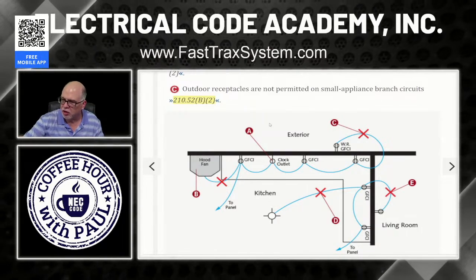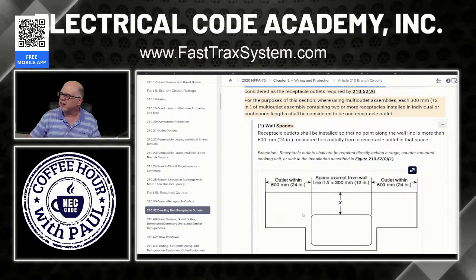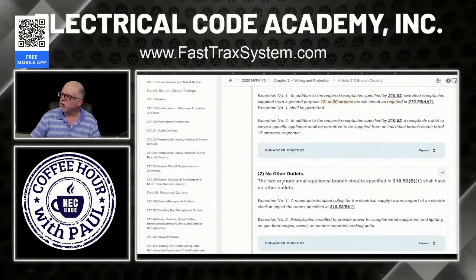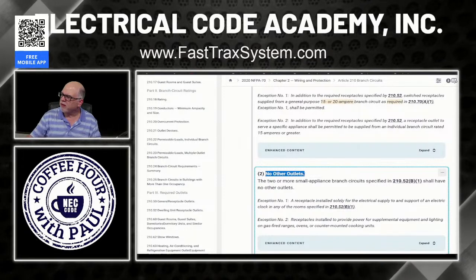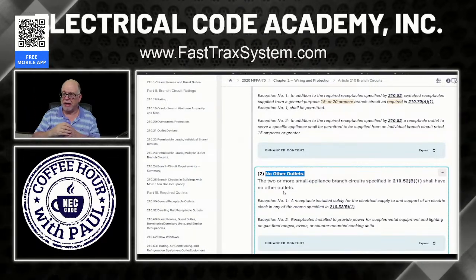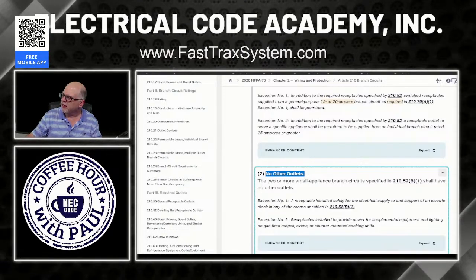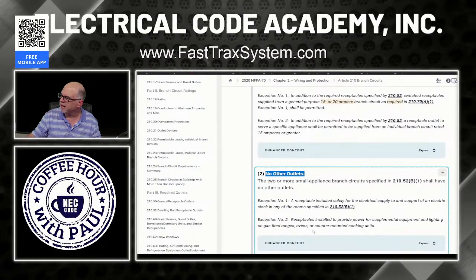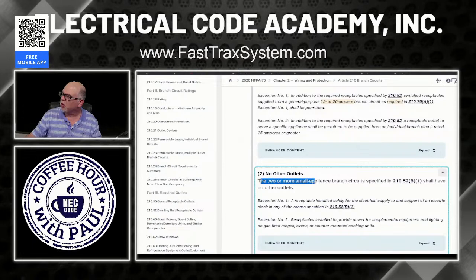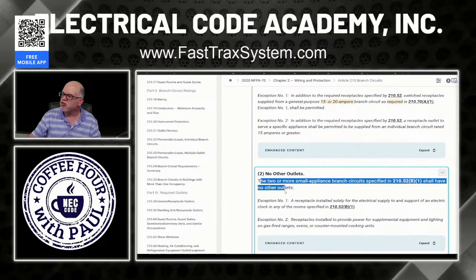Okay, so let's go to the code, 210.52(B)(2), and I will show you that to show you understand that that's what it says. 210.52, and we'll go down here to (B)(2). No other outlets. Now, when we see no other outlets, folks, that means no lighting outlets, no other outlets outside, those types of things. And here are the exceptions that we've been talking about right here. It says the two or more small appliance branch circuits specified in 210.52(B)(1) shall have no other outlets.